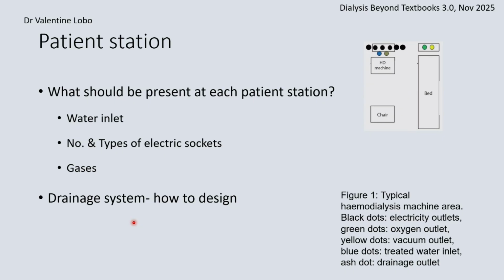Of course, there has to be a water inlet. Electrical sockets. As I just said, in addition to the dialysis machine, you would probably have a cardiac monitor. You may have a syringe pump or an infusion pump running in some situations, because patients are getting either nutrition or some drugs. So you would have to have additional electrical sockets for that. The ISN guideline therefore recommends 5 to 6 as the minimum number of electrical sockets per bed. Medical gases should be available: oxygen, air and vacuum, and suction if possible.